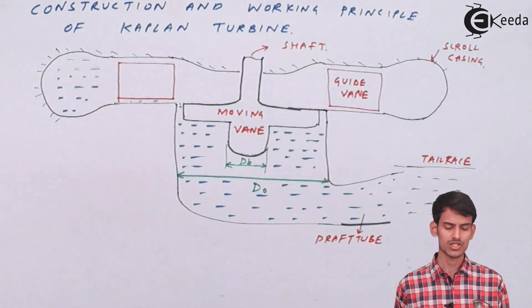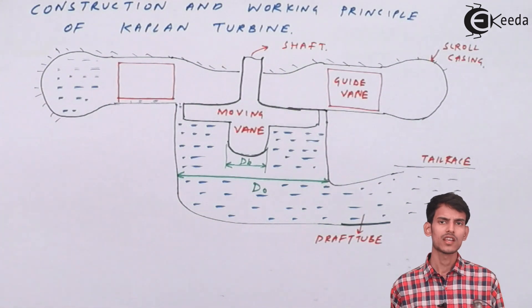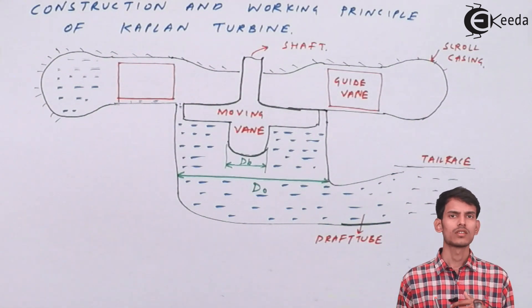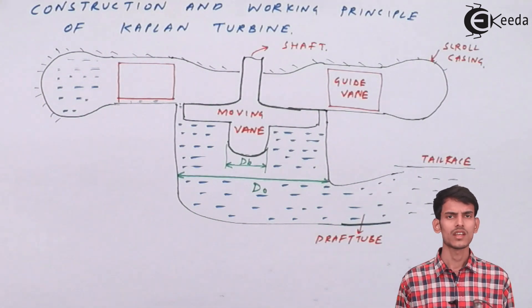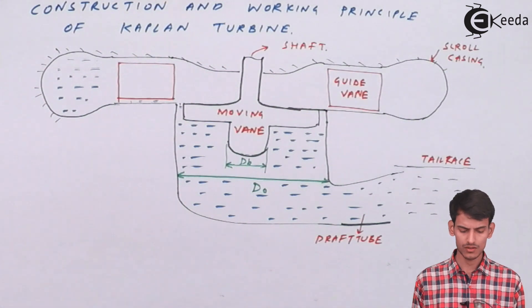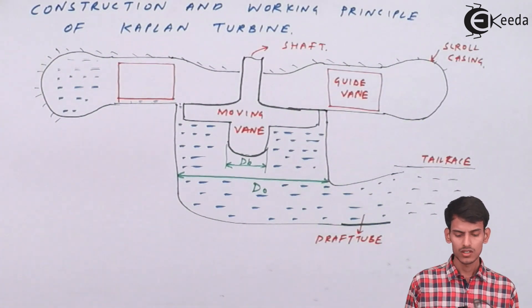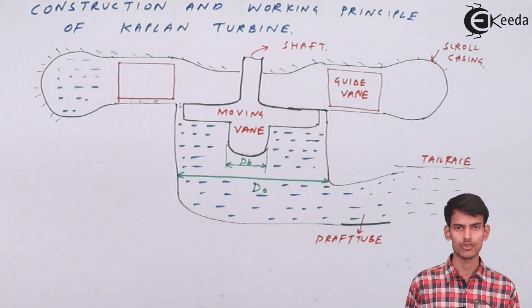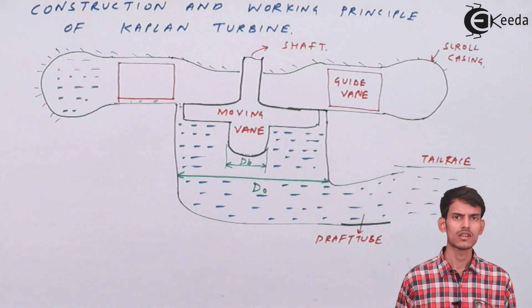The area available for discharge can be easily calculated: D0 is the outer diameter of the impeller and Db is the diameter of the hub, so the difference in areas gives the space available for water at the inlet side. The area is calculated as π/4 × (D0² − Db²). The working is mostly similar to the Francis turbine. The only difference is that the vanes here are movable — you can adjust them. There is also scroll casing, a shaft, and a draft tube. That covers the construction and working of the Kaplan turbine.